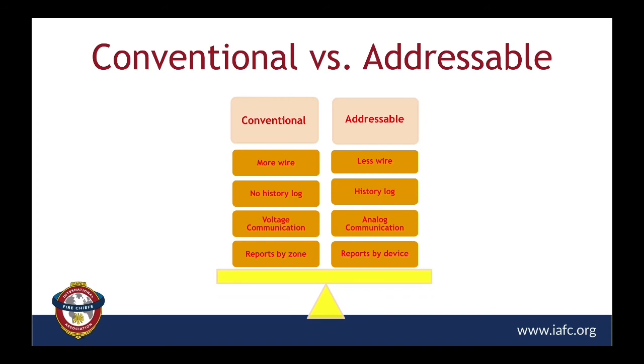Next slide. Dan, I think you bring up some good points, because sometimes the fire service has to help the building owner and the fire alarm contractor play detective. Why are we getting false alarms? Why are we getting activation of systems? Right. And I think this is a great point about marking the zone and the device in the fire report. That way, if we ever have to go back and play fire investigator, or figure out what is creating the false alarms, we have some kind of history.